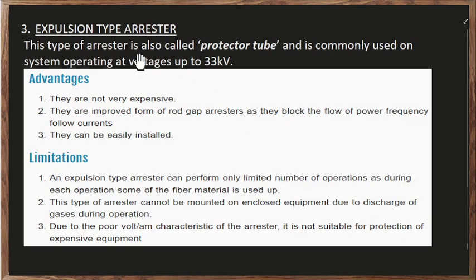Then you have the expulsion type arrestor. This type of arrestor is also called a protector tube and is commonly used on systems operating at voltages up to 33 kilovolts. Now, the advantages are they are not very expensive. They are an improved form of rod gap arrestor, and they can be easily installed. The limitation is that the expulsion type arrestor can only perform a limited number of operations. And this type of arrestor cannot be mounted on enclosed equipment due to discharge gases during operation.